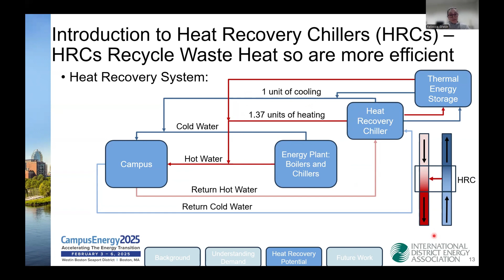With that, you're able to produce 1 unit of cooling for every 1.37 units of heating. That means you are no longer wasting that excess heat from the cold water. You are able to transfer that excess heat into the hot water stream, and with that, you are more efficient. But in order to optimally use the heat recovery chillers, it's often necessary to have thermal energy storage. So for the rest of this presentation, I'm assuming that all the needed storage to optimally use the heat recovery chillers is available. And this 1.37 units of heating for every unit of cooling is a rule of thumb that is commonly used in the field.